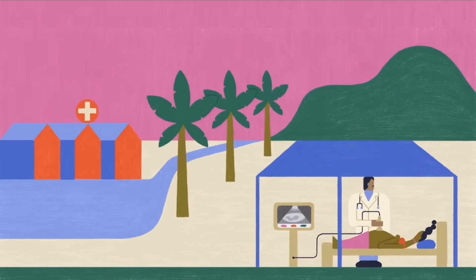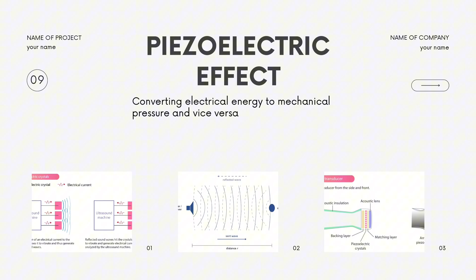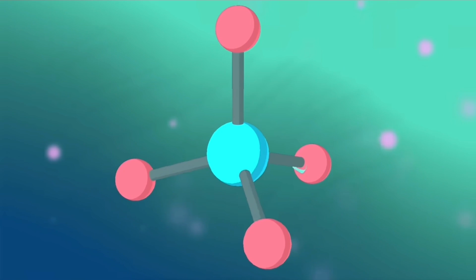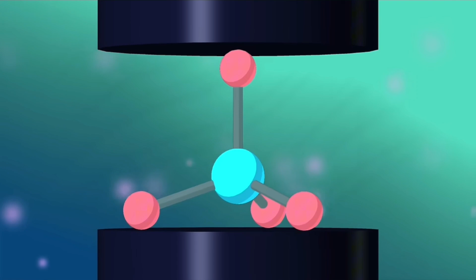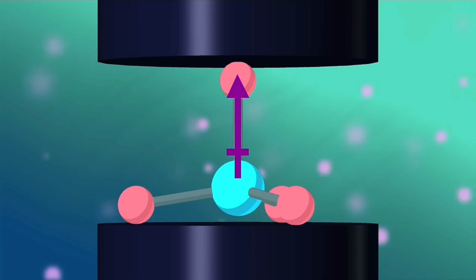Other than that, we have the generation of ultrasound waves. What is the piezoelectric effect? It is converting electrical energy to mechanical pressure and vice versa. Let's look at quartz, a piezoelectric material made of silicon and oxygen. The oxygens have a slight negative charge and the silicons have a slight positive charge, creating a separation of charge, or a dipole, along each bond. Normally, these dipoles cancel each other out, so there is no net separation of charge in the unit cell. But if a quartz crystal is squeezed along a certain direction, the atoms shift. Because of the resulting asymmetry in charge distribution, the dipoles no longer cancel each other out.